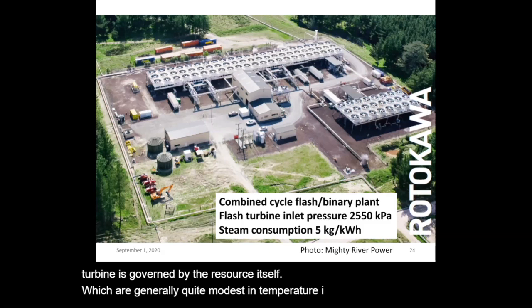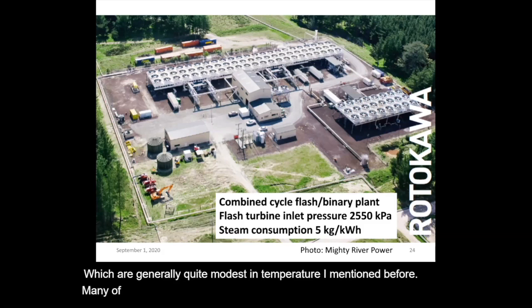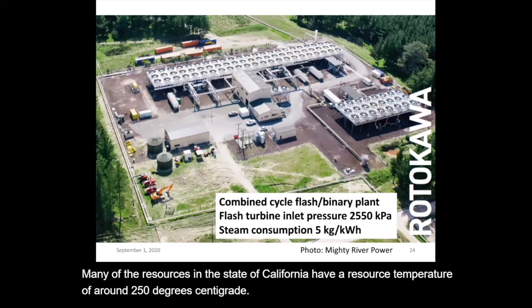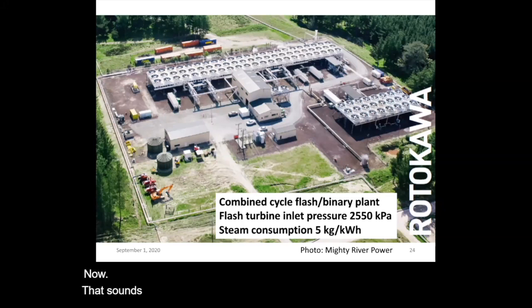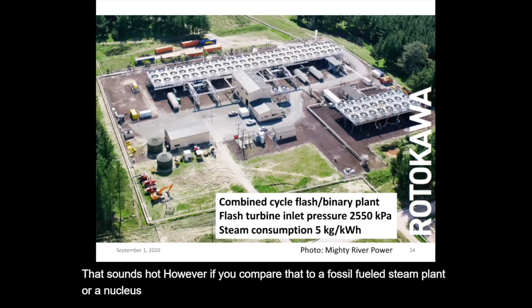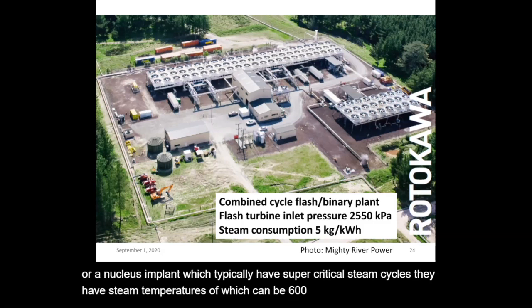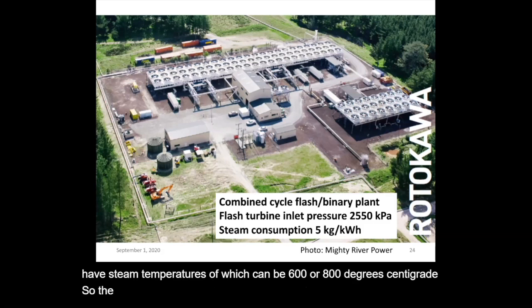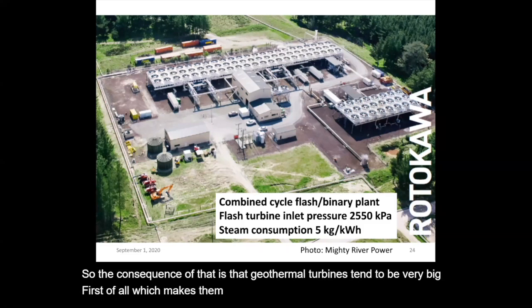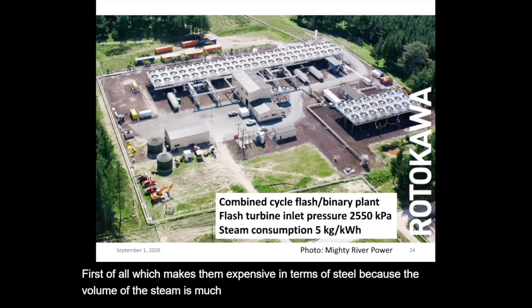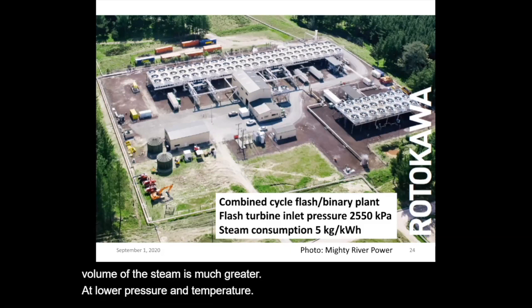I mentioned before, many of the resources in the state of California have a resource temperature of around 250 degrees centigrade. That sounds hot, however, if you compare that to a fossil-fueled steam plant or a nuclear steam plant, which typically have supercritical steam cycles, they have steam temperatures which can be 600 or 800 degrees centigrade. The consequence is that geothermal turbines tend to be very big, which makes them expensive in terms of steel, because the volume of the steam is much greater at lower pressure and temperature. Secondly, their efficiency is less because of the lower pressure.